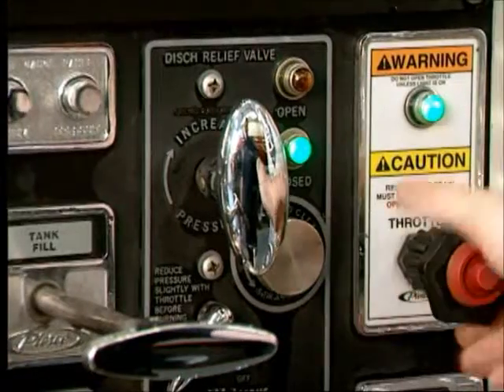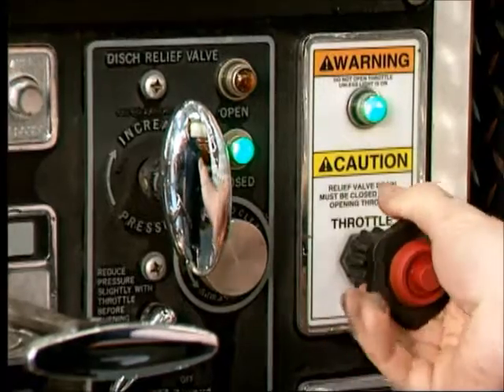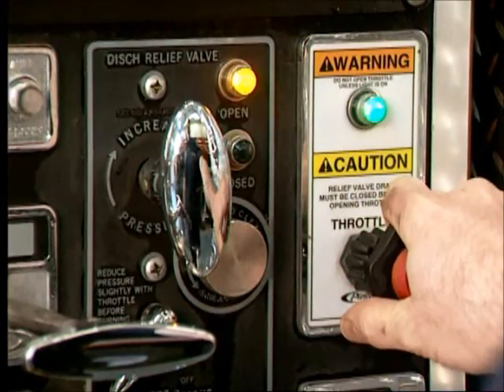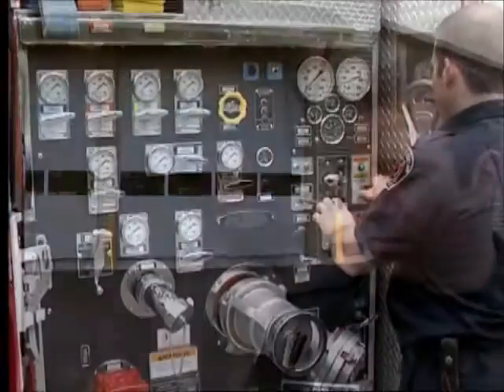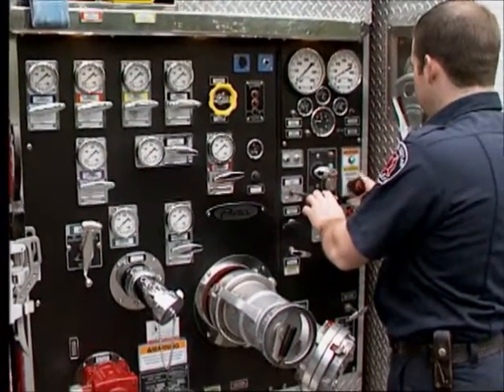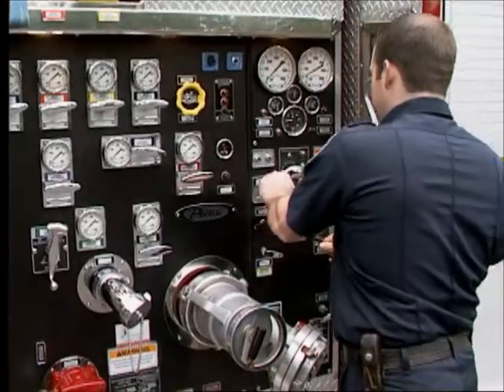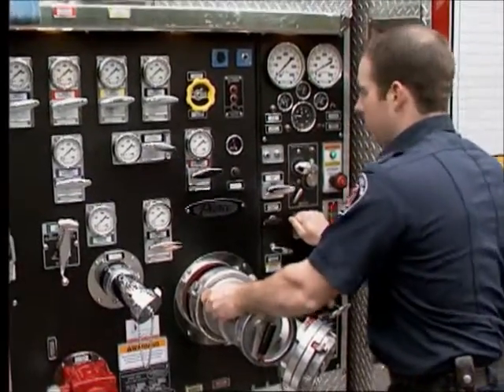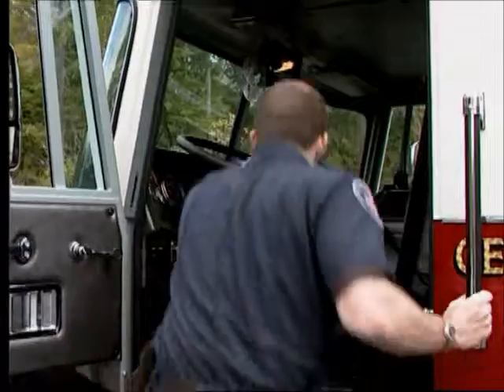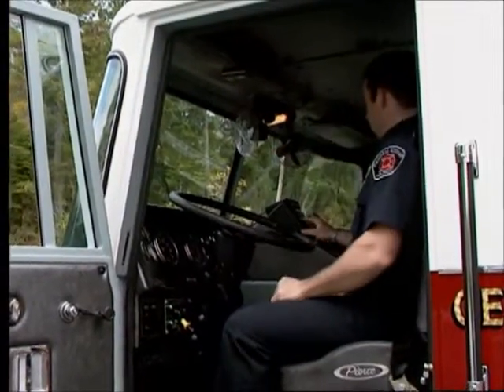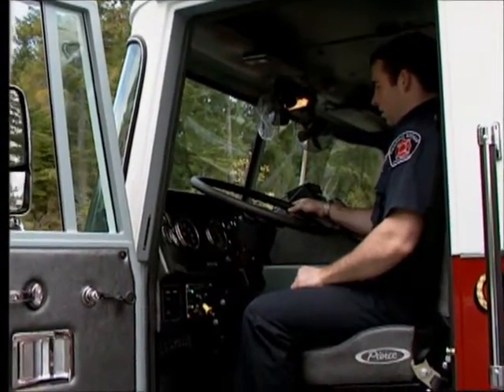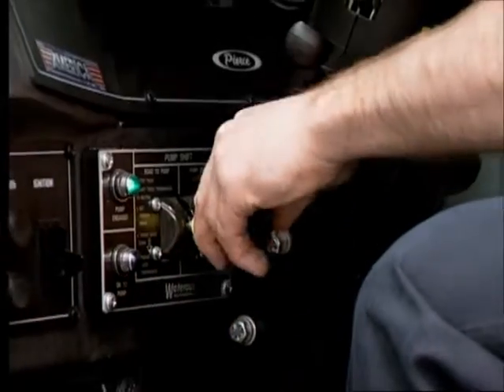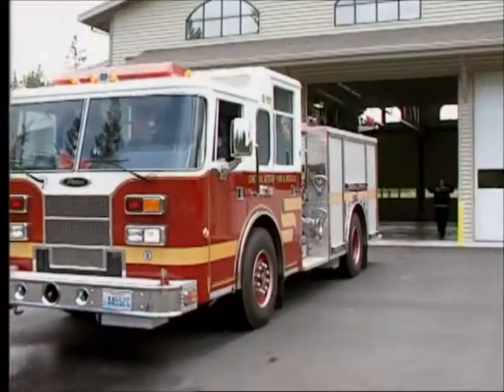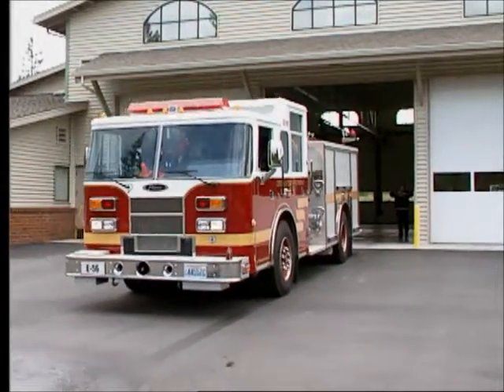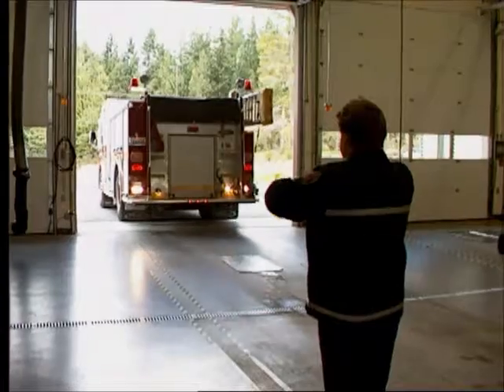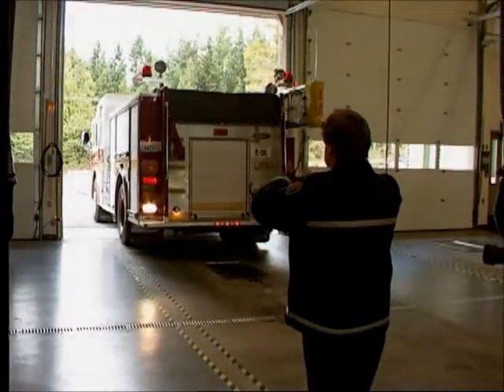Operate all of the valves, including the relief valve or governor, each week. Periodically, you should have the pump gearbox checked for the proper oil level. Also check for traces of water. Read the manufacturer's recommendations for additional maintenance or inspection instructions. Once a year, the pump should be completely service tested according to NFPA Standard 1911. All gauges should be checked against a test gauge to be certain they are registering correctly.